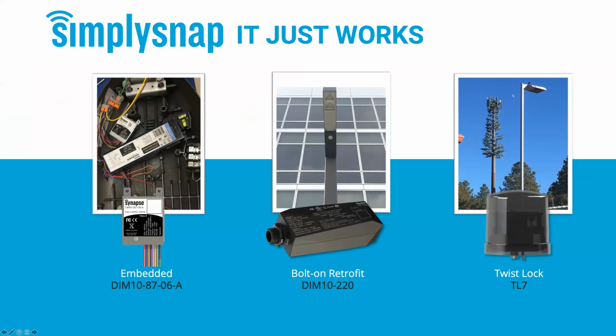The picture on the left shows an example of inside of a light, how our controller would be integrated, connected up, talking to the driver. For LED retrofits, we do have the IP65 rated controller, the DIMM-10 220. It can be mounted on a pole or mounted directly to the light with a 1/2-inch nipple connector. Our twist lock controllers have a 277/480 volt version that'll fit any standard NEMA socket.